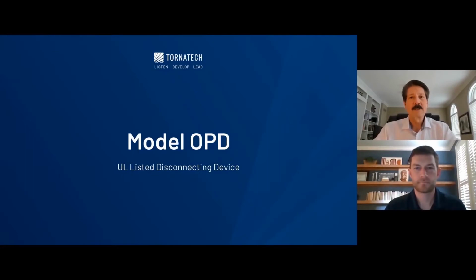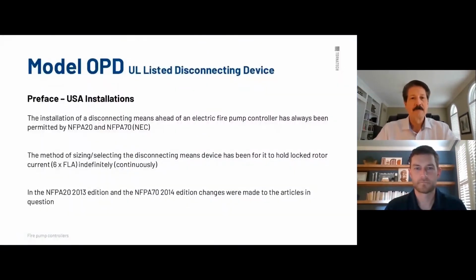Welcome, everyone, to our presentation. Let's get right into it. The OPD, Overcurrent Protective Device. This is a UL-listed disconnecting device. As you can see, the installation of a disconnecting means ahead of an electric fire pump controller has always been permitted by NFPA 20 and referencing NFPA 70/NEC. This is critical because it's been around for a long time and it's finally getting into this side of the business on our fire protection systems.